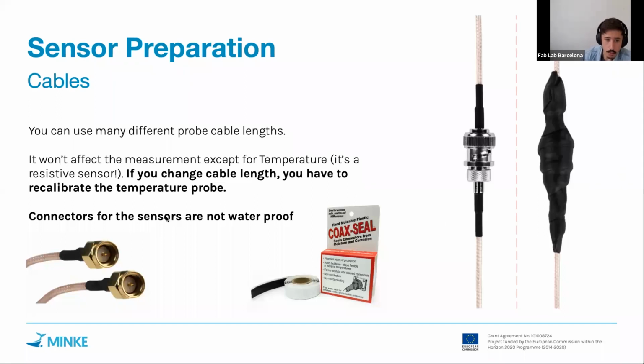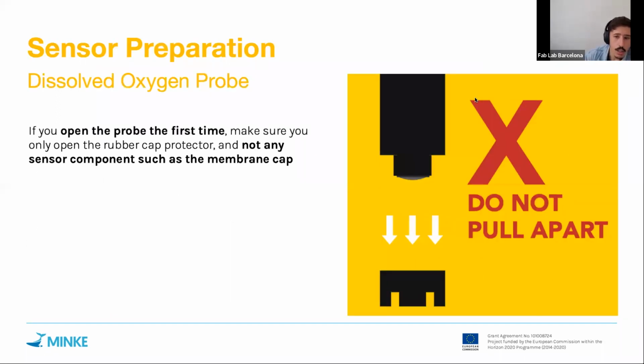Important is that, of course, these connectors are not waterproof, but also that in the case of the temperature probe, since it's a resistive sensor, we need to recalibrate. So if you change the cable, you need to recalibrate it, because we are affecting the measurements directly by extending the cable, adding more resistance with a new cable, or removing it.